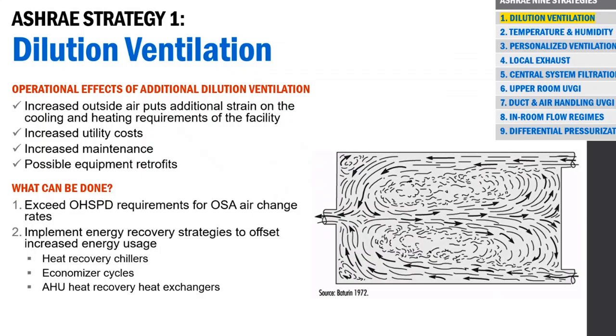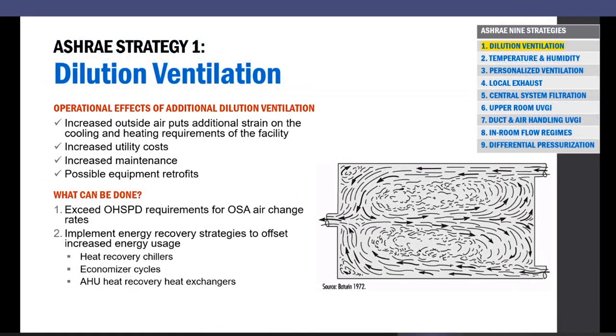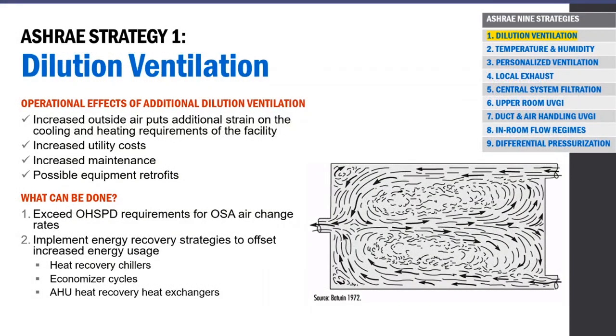We have the minimum requirements in the California Mechanical Code. If we increase above and beyond the required minimums, there are some impacts that have to be accounted for. Additional outside air is going to put strain on your existing air handling equipment to maintain heating and cooling for the space, so that needs to be considered when we implement the dilution strategy. There are ways to offset the impact: heat recovery, economizers in your air handling equipment, heat recovery at the main central plant equipment to recover that energy, so we're not increasing utility costs and maintenance.